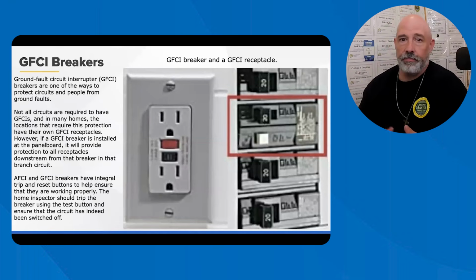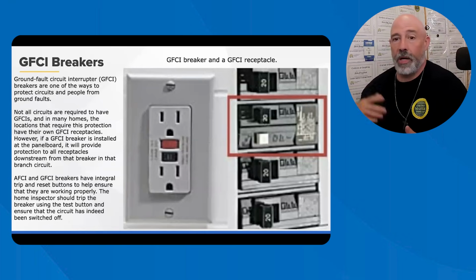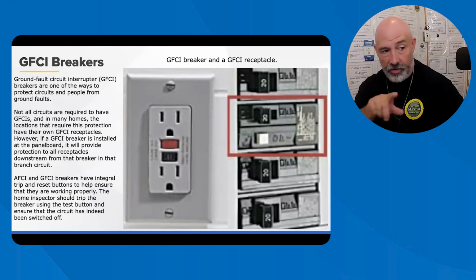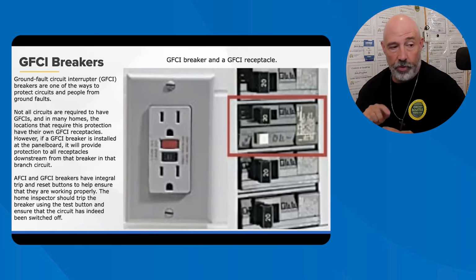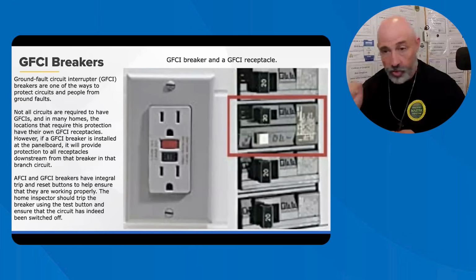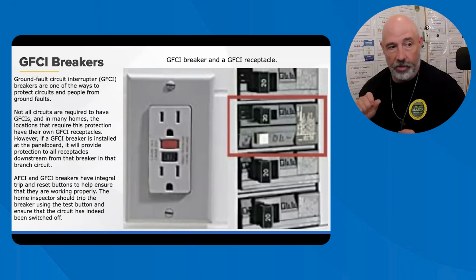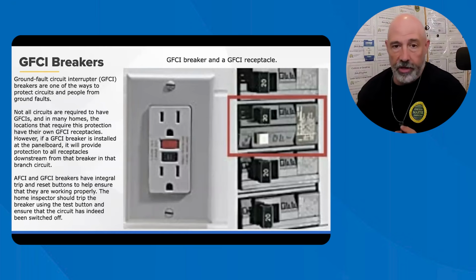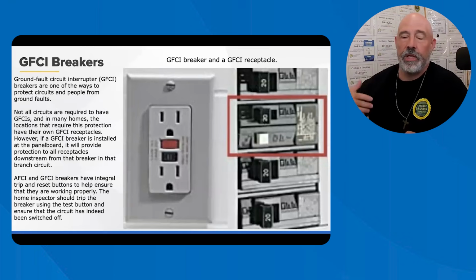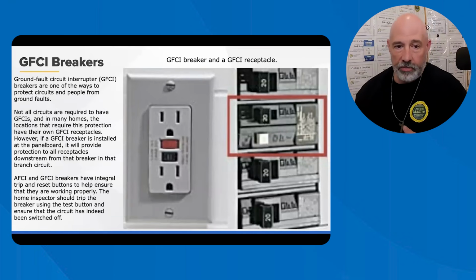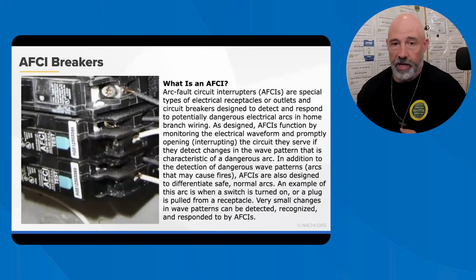GFCIs are found either in the panel or on the outlet itself. I always check these to make sure that they're working. If you push the test button and it doesn't trip, trip it manually and then come back, because sometimes it'll break right there. If it doesn't trip, just turn it off and then turn it back on. That way it still is a circuit breaker, but the GFCI is not working. Make sure you call that out as a fault. I recommend to my customers to trip them twice a year when you change the smoke alarm batteries. So that's kind of my thought.